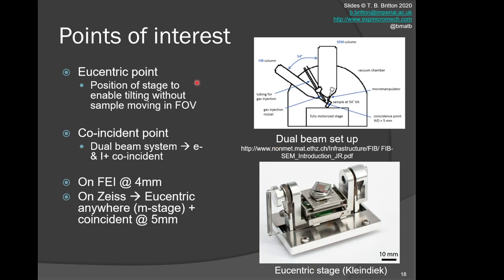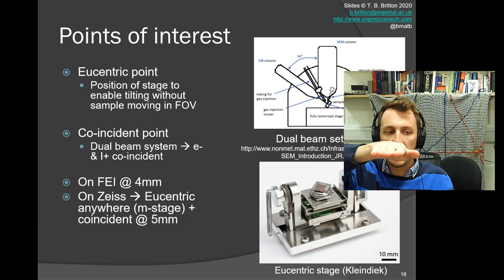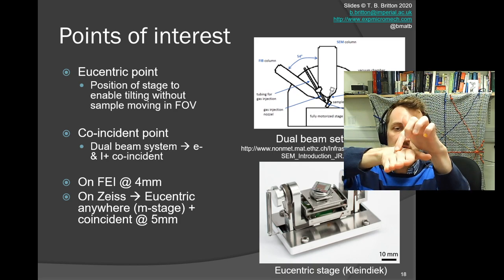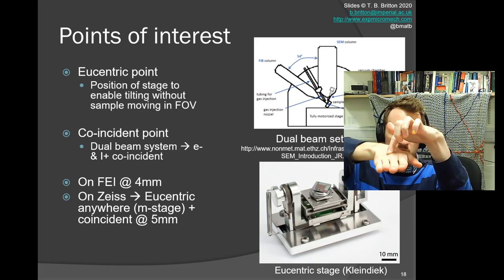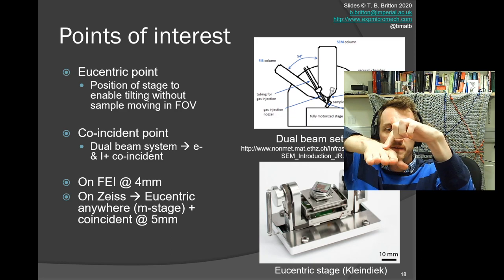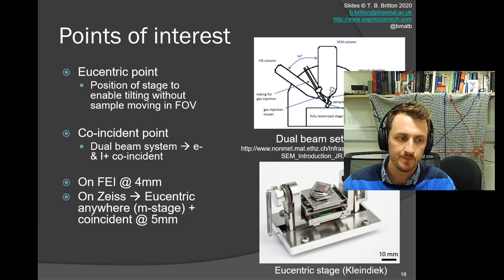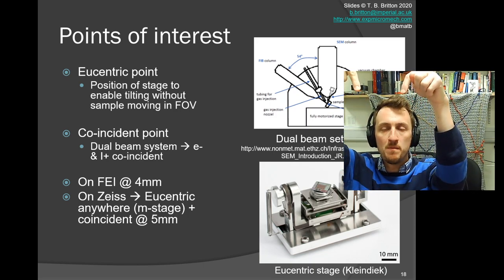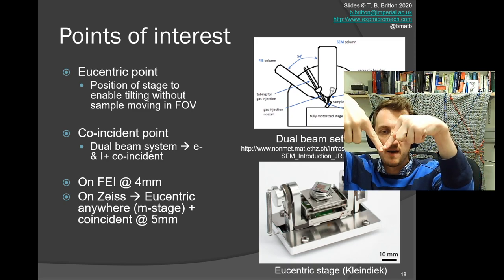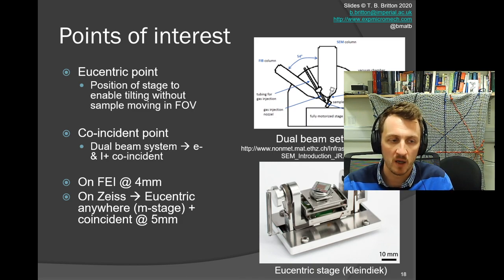In dual beam instruments, we have a variety of points of interest. First is the eucentric point. The eucentric point is that we're going to tilt—the eucentric point is the position that remains constant with respect to our stage as we tilt it. So if I tilted and had this as eucentric, my middle knuckle—I'm keeping that steady—that's my eucentric point. If I've got my two beams, for instance in a dual beam instrument, I will have a second point called the coincident point. That's where the electron beam and the ion beam are coincident.